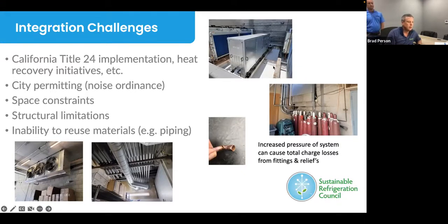In the top picture, that's a rooftop over an adjacent multi-story building next to the store, with a parking garage and residential tenants. We used this spot because it was the existing location with an expansive framework already built over that roof line as a halo. We looked at how to incorporate that same location, since it has natural sound mitigation from the wall right behind it, with an auto garage where the camera person is standing. We had to modify that framework and analyze the loads through the project phases to make sure we weren't overstressing any part, as we replaced the standard DX system with a closed loop water pre-cooled tower at the facility and pump station.